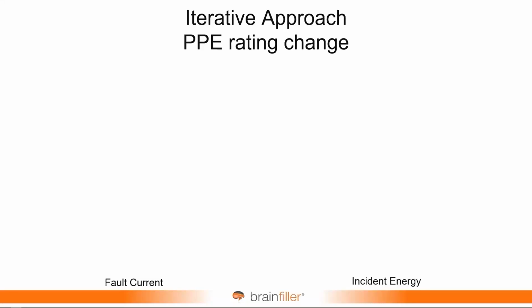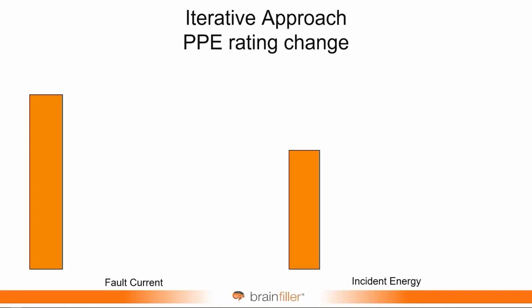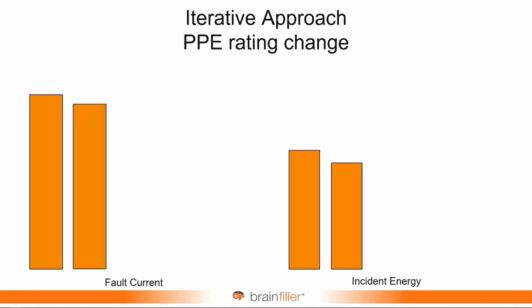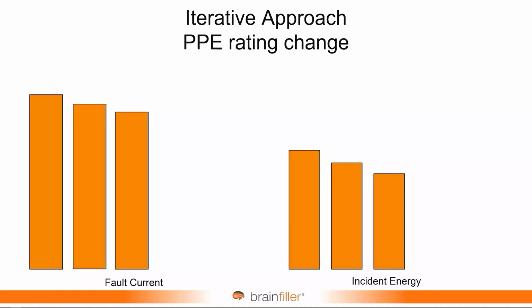Sometimes people will question, well, I don't actually know the actual fault current from the utility, or it could vary or something like that. So for years now, I've been advocating, in that case, it's not a perfect answer, but perhaps use an iterative kind of approach. What that is, you begin with the initial fault current, basically the highest fault current, and you conduct your study, and you'll get a resulting incident energy. And then take that fault current and reduce it in incremental steps, 5 or 10%. What will happen is you'll see the incident energy also reduce. And you continue to reduce the fault current. The incident energy continues to reduce.